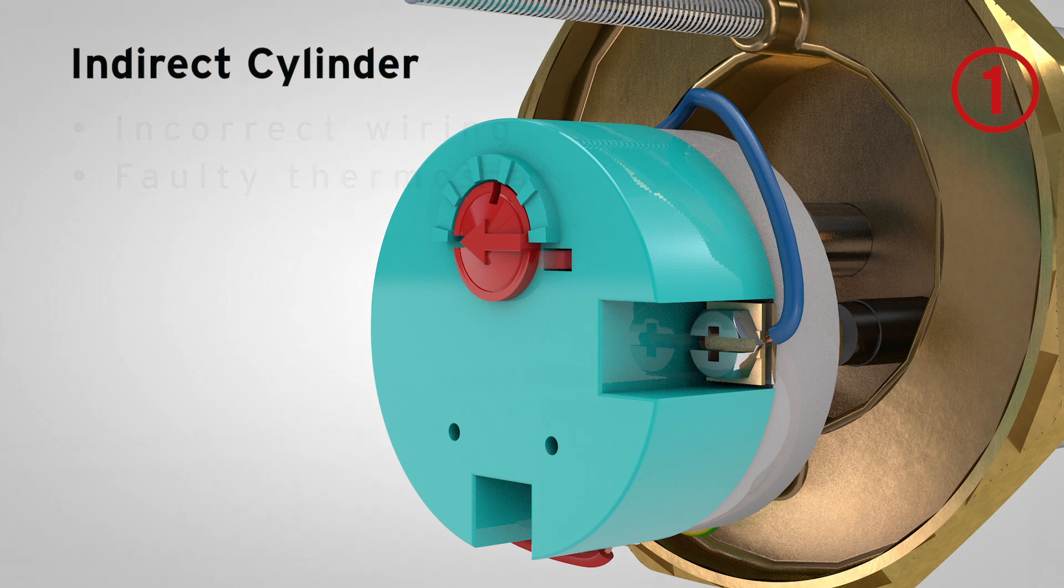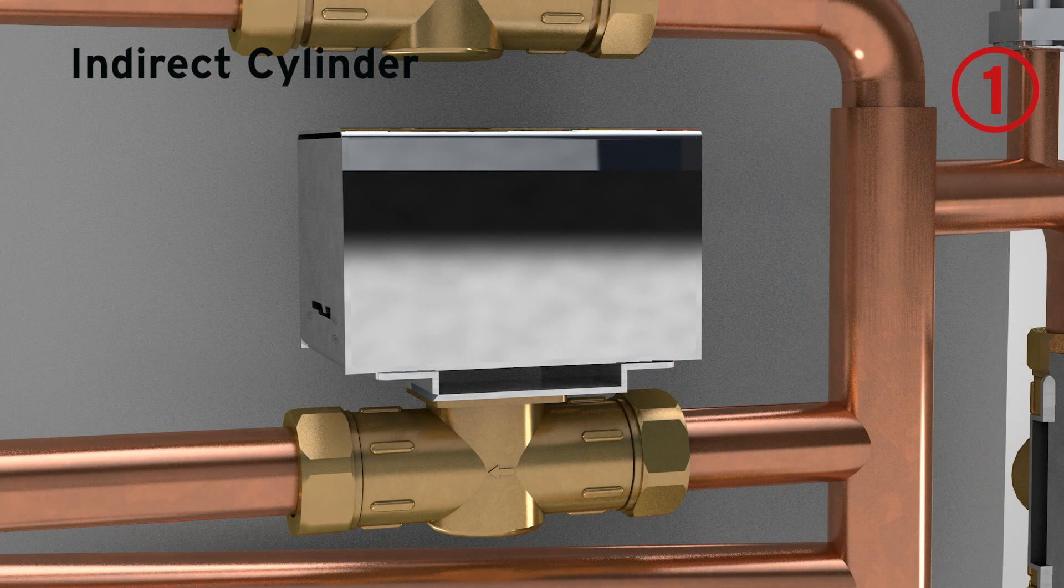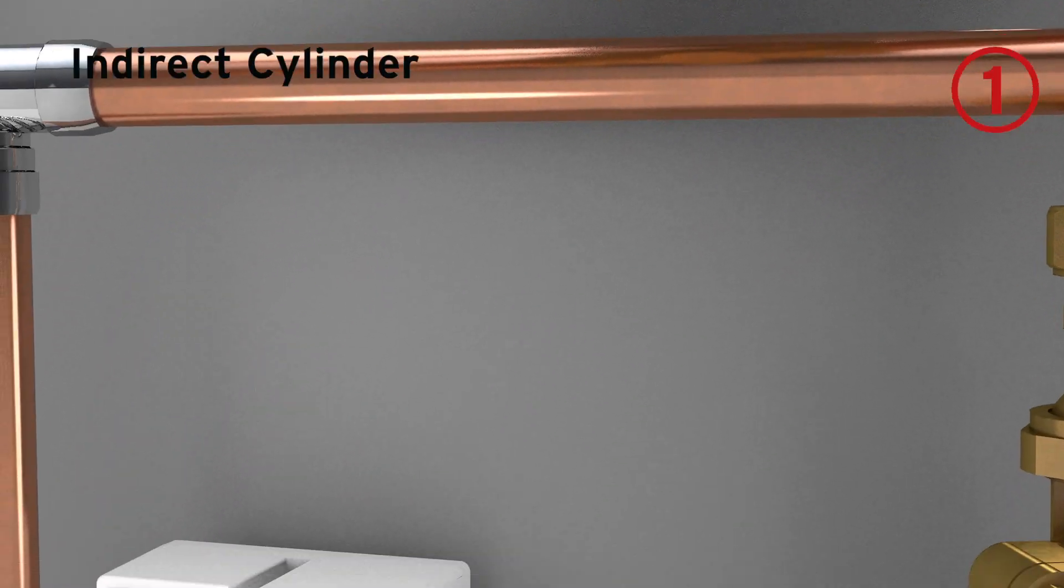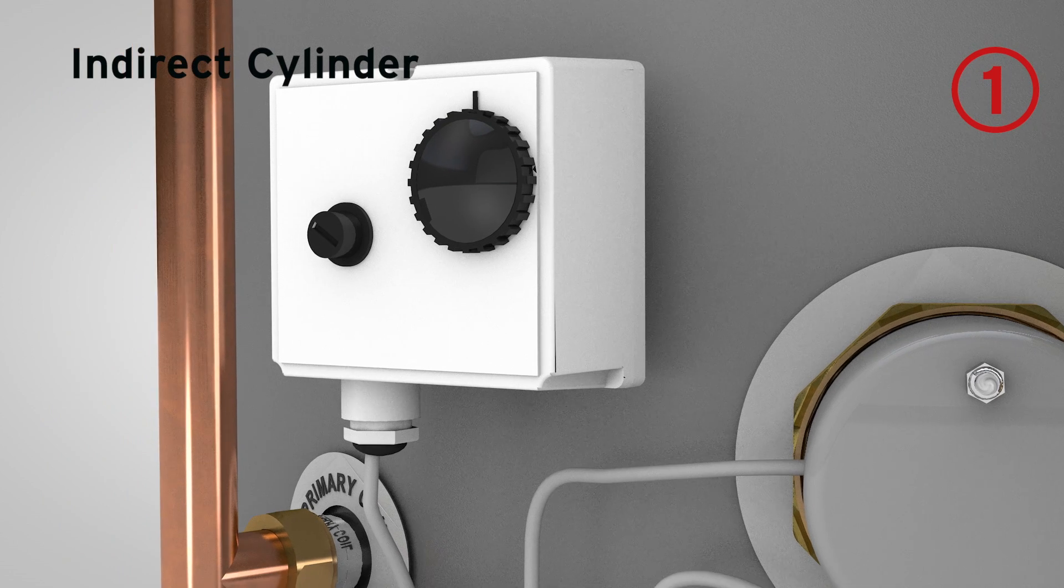On an indirect cylinder, you will need to check the two port valve, as it may be jammed open or the actuator failed, causing the cylinder to overheat. Or, the control thermostat to the boiler may have failed.